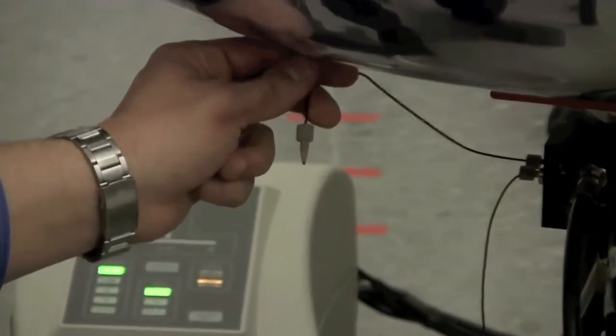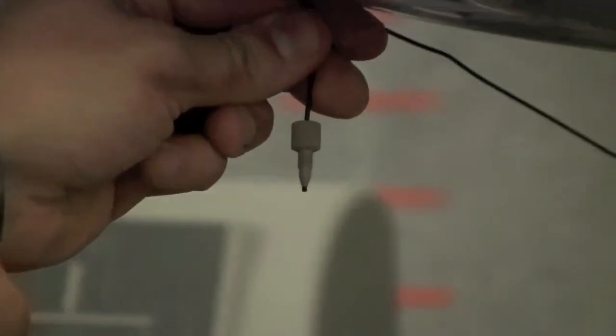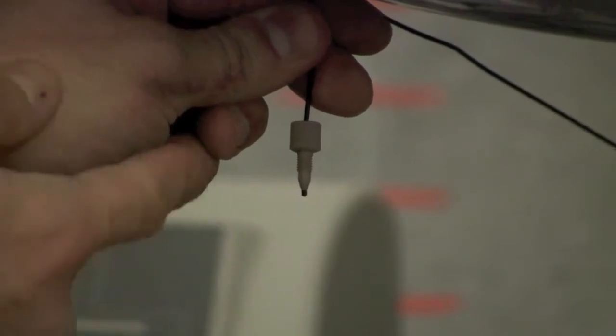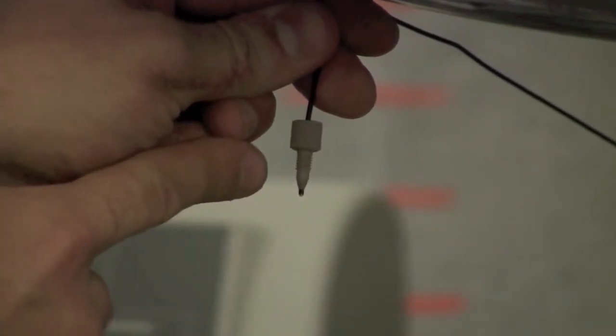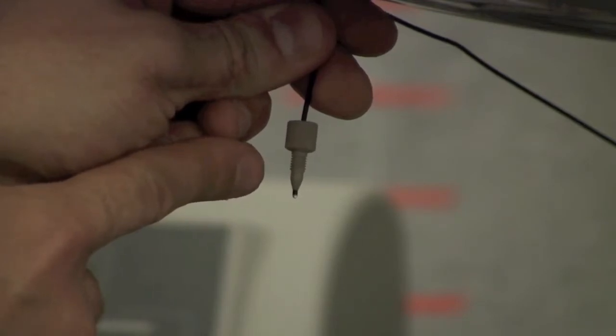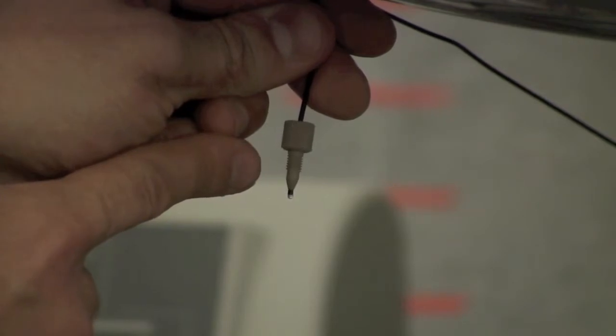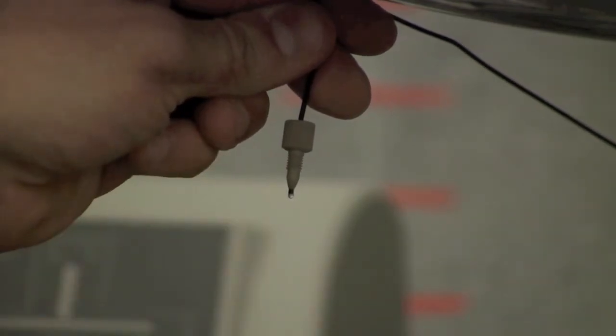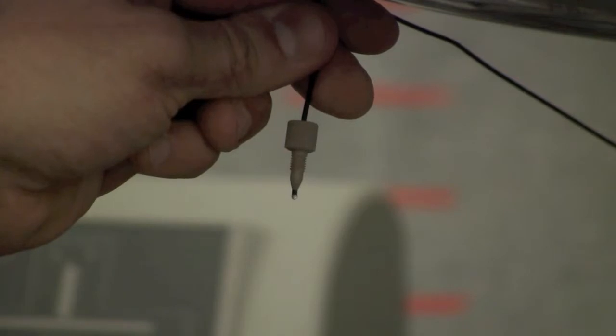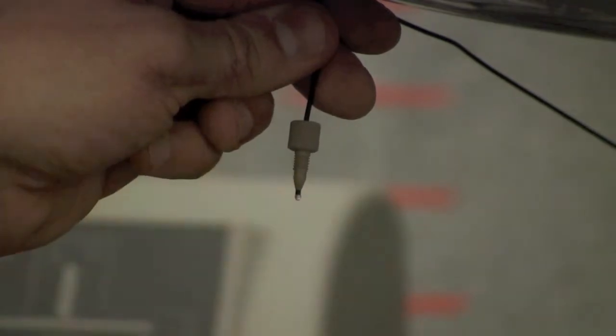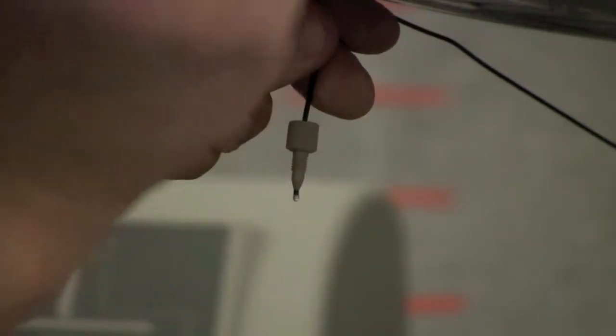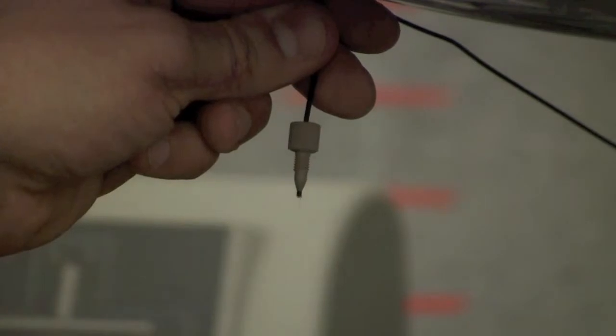It takes a while for the solvent to come out. And what you should see is initially a bubble starts to form on the outlet of the line here. That bubble will grow larger and larger as the air slowly pushes it out. Remember that the lines are very, very small in diameter. This is why we need to always have our samples filtered, because it can easily clog the lines. The reason they're so small is that we want all of our sample to be up in the coil and not waste very much sample on the way out.